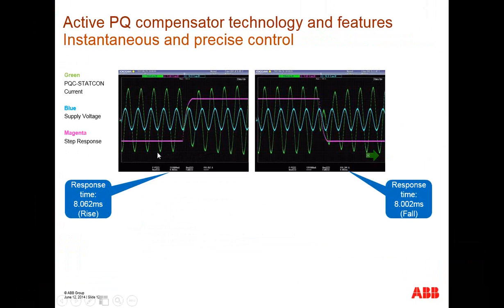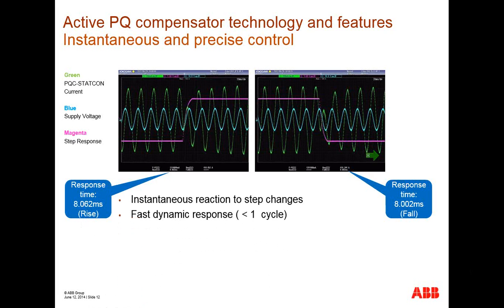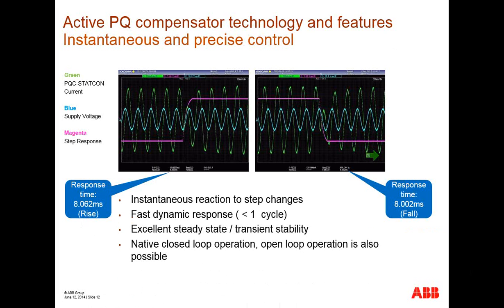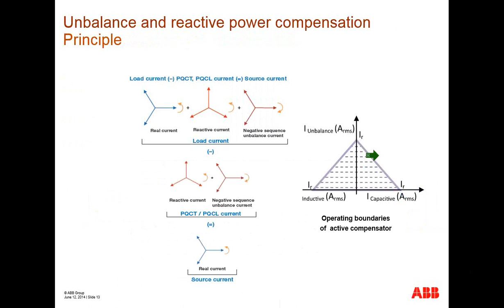We can see here the response time when we talk about going from inductive power to capacitive power. It takes just less than a cycle. Similarly, when it goes from capacitive load to inductive load, that is also taking less than a cycle response time. So its reaction is very instantaneous, with step change, very fast dynamic response, and excellent steady state and transient performance. Even during the changes, you can see the current response is sinusoidal in nature. We can see it can work both in closed loop as well as open loop, and with four cascade control loops in the system. And this system can work both.